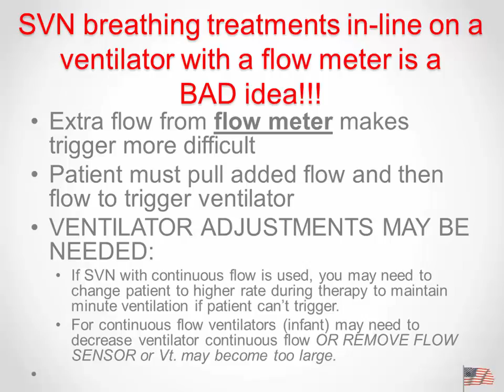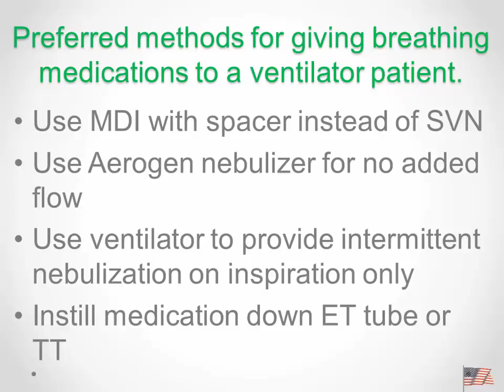especially with continuous flow systems like we see on infant ventilators, you may need to adjust the continuous flow downward to compensate for the flow that we're adding into the circuitry. You can also use an MDI. We can use an Aerogen nebulizer, which is an ultrasonic. It's not truly, but it's along that line. In other words, there's no bias flow being added. If you have a ventilator that has the ability to provide flow only on inspiration, some of them will only power the nebulizer during inspiration, or you can instill the medication. That's not that commonly done. But the first two are your two most common ways that we can combat this problem.